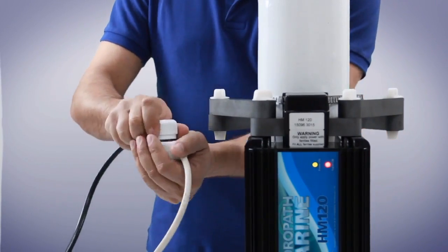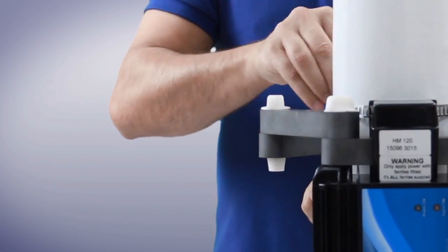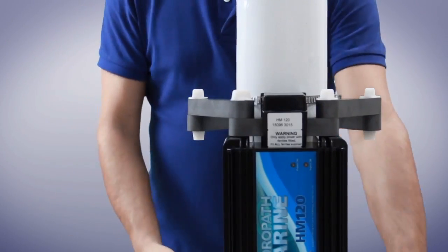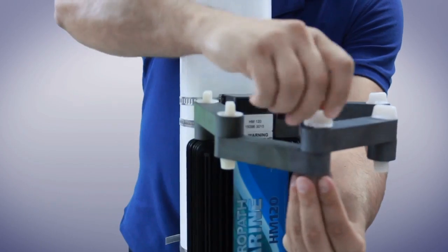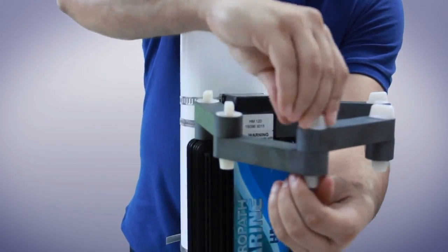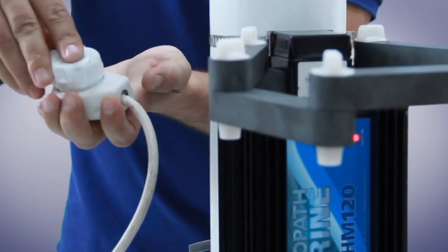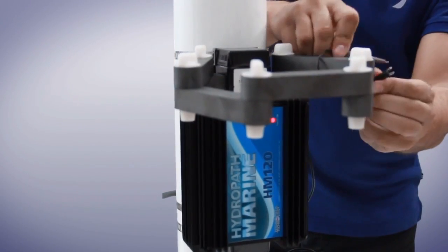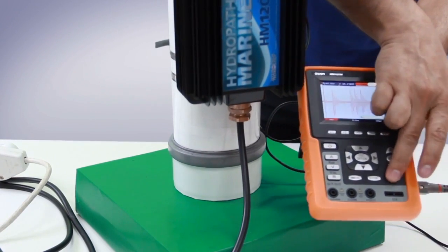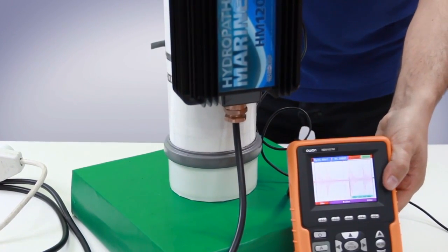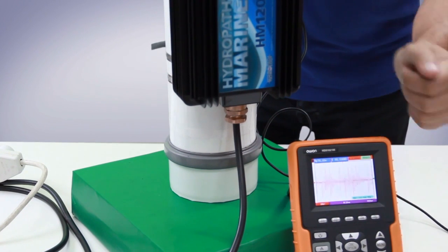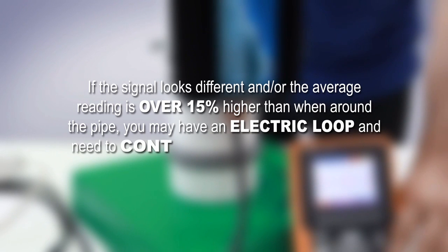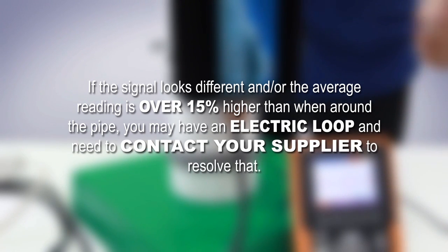If you are not sure whether the signal is correct, you can unplug the unit from the power, open the ferrite ring and close it again without the pipe. Then connect the unit to the power and recheck it with the oscilloscope. Use the Run Stop button and write the voltage reading and repeat 3 times to get an average reading. If the signal looks different and/or the average reading is over 15% higher than when around the pipe, you may have an electric loop and need to contact your supplier to resolve that.